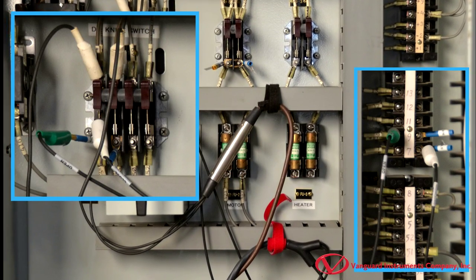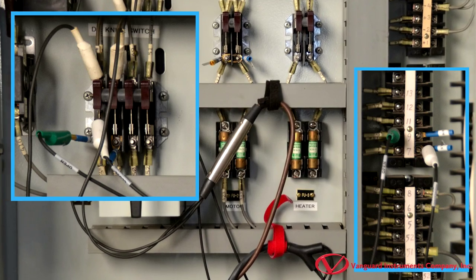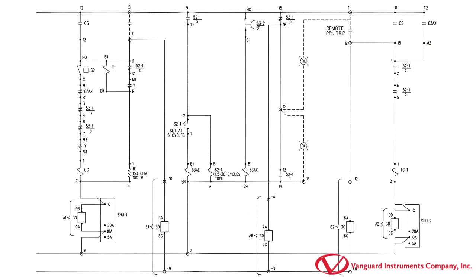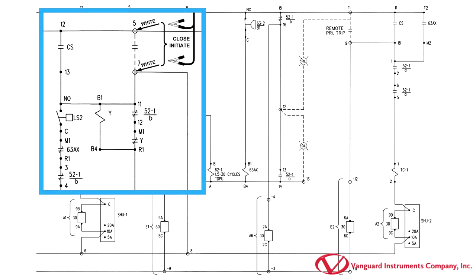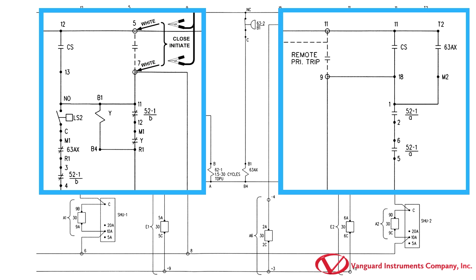The initiate circuit acts like a switch to energize the trip or close coil. In this illustration, the initiate circuit will connect terminal 5, which is the positive DC source, to terminal 7 of the circuit breaker closed circuit. On the trip circuit, the initiate circuit will connect the positive DC supply to terminal 9 of the trip circuit.